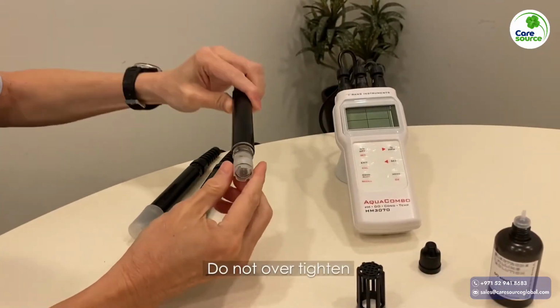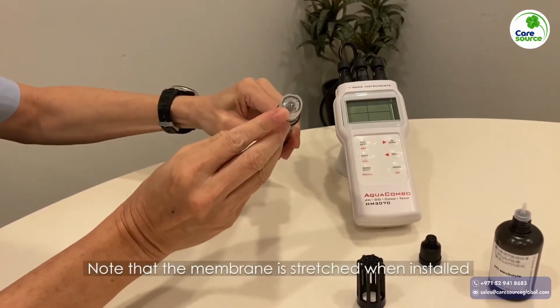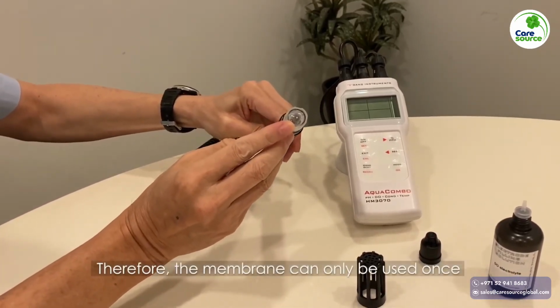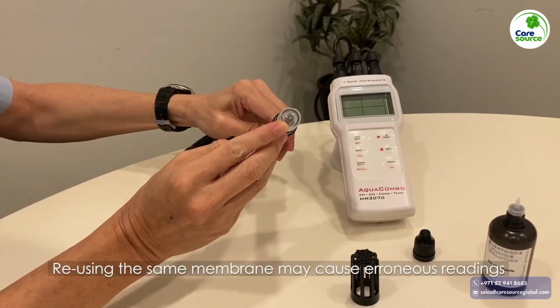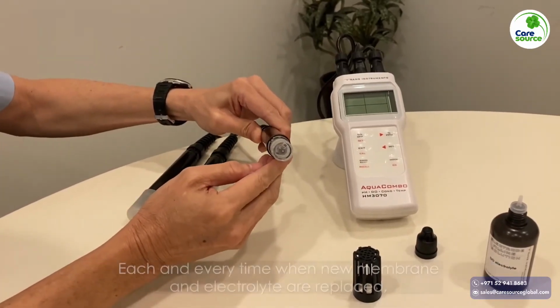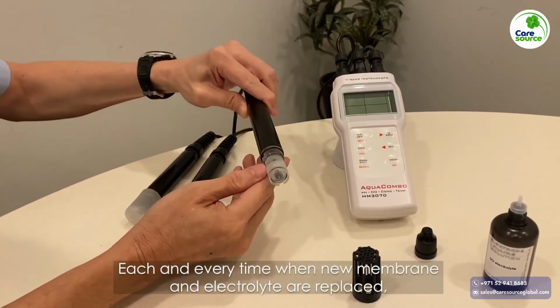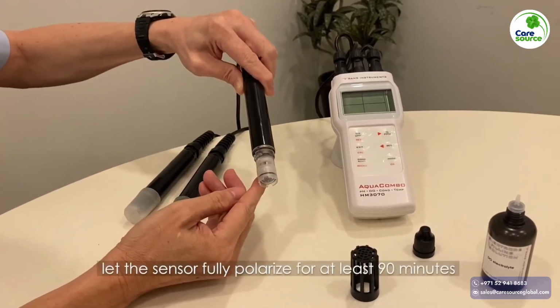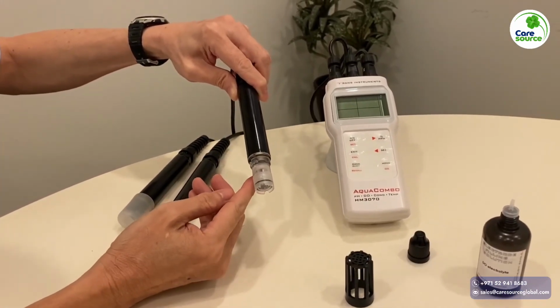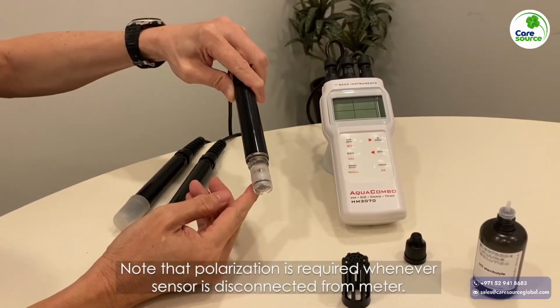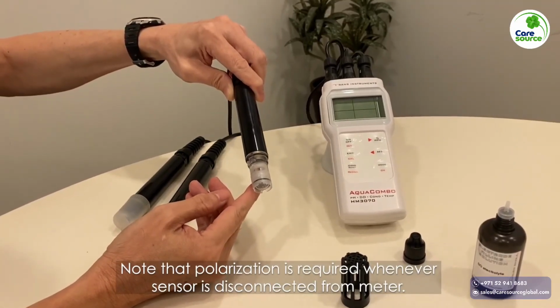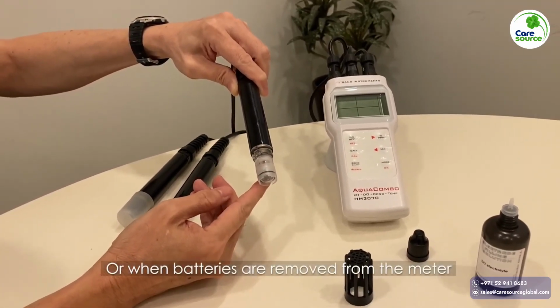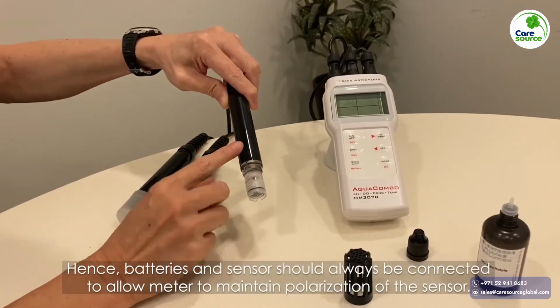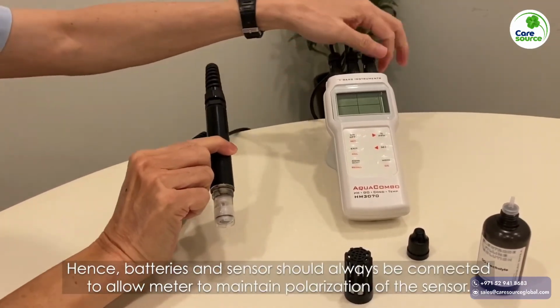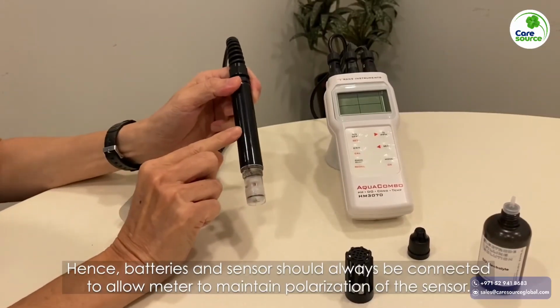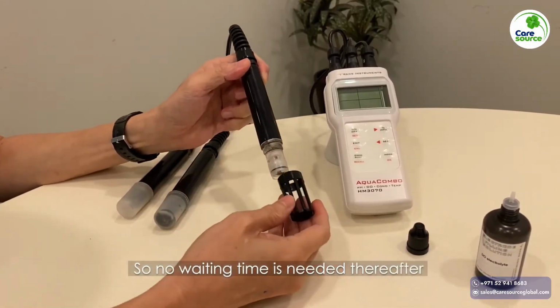Do not over-tighten. Note that the membrane is stretched while installed. Therefore, the membrane can only be used once, and reusing the same membrane may cause erroneous readings. Each and every time new membrane and electrolyte are replaced, let the sensor fully polarize for at least 90 minutes. Note that polarization is required whenever the sensor is disconnected from the meter or when batteries are removed from the meter. Hence, batteries and sensor should always be connected to allow the meter to maintain polarization of the sensor, so no waiting time is needed thereafter.